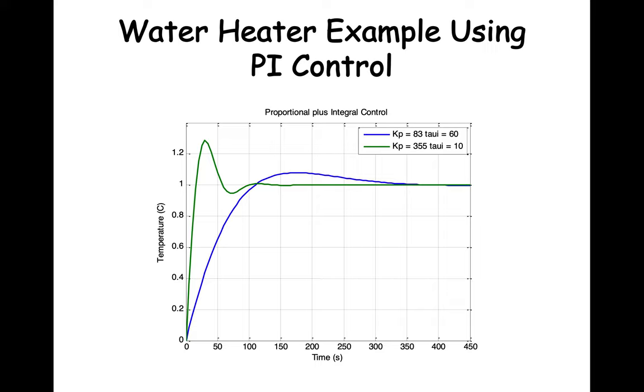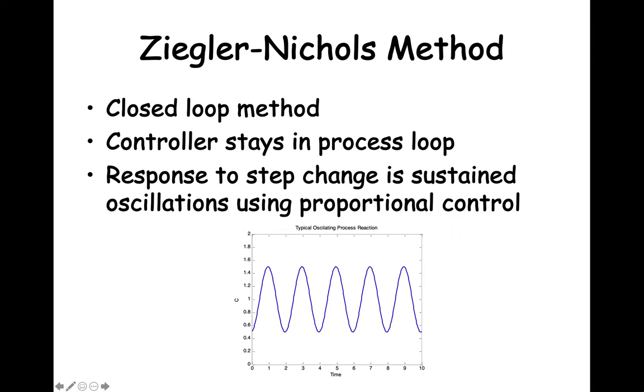So the Cohen-Coon method produced good process control results. The other method for controller tuning is the Ziegler-Nichols method. This method is sometimes called the closed loop method because the controller stays in the process loop. The controller is set up to run using proportional control only, and the process is subjected to small step changes to produce sustained oscillations in the response.